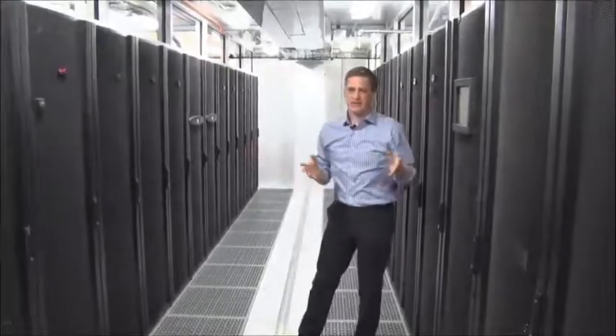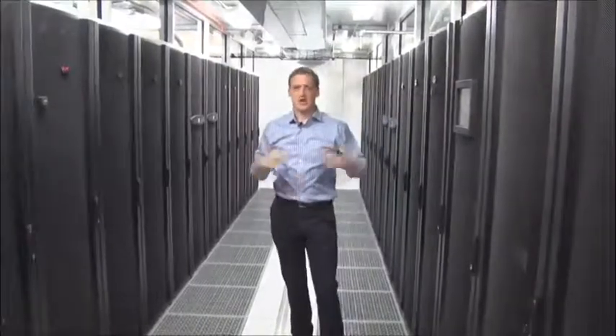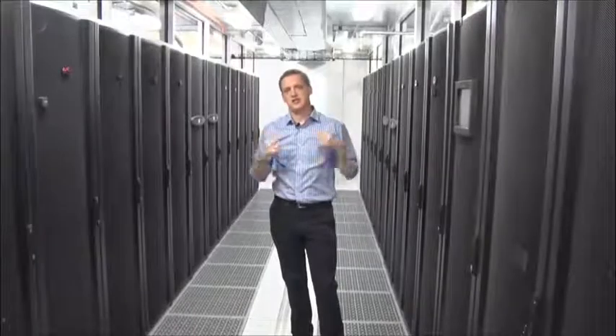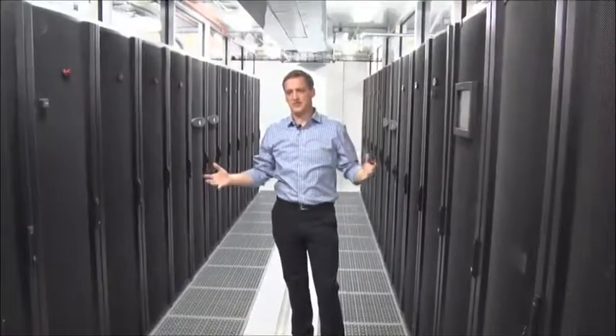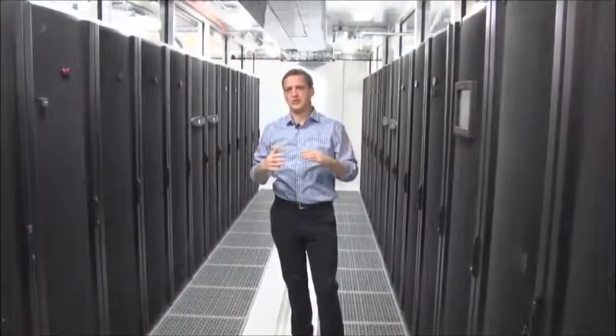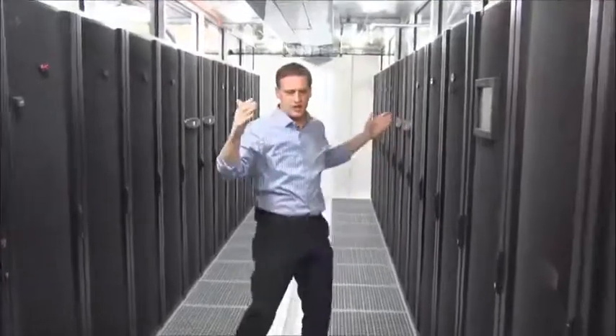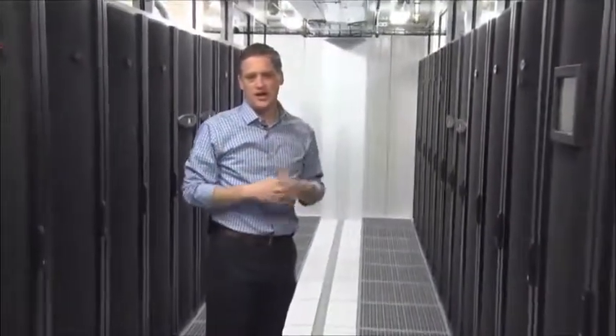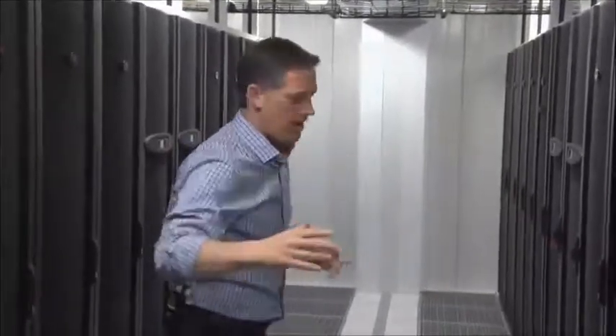When I say what fits, that's probably the biggest exercise we go through when designing these - trying to figure out, given your specs, what you want to build and what we can actually fit in a module. Here's one of the challenges: because we're going with a set length or set width of module - and I say set, we have flexibility to modify that as well - we tend to try and stay within our set sizes of a 25-foot or a 45-foot long module. And that fits only so many racks and cooling units.